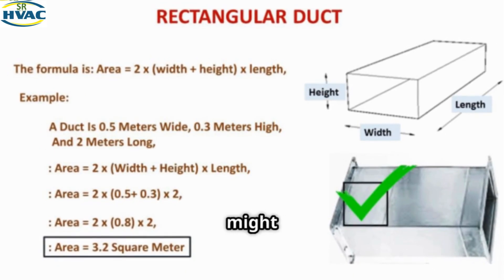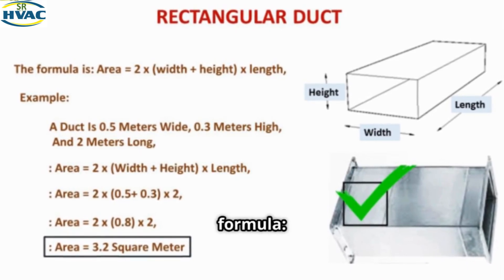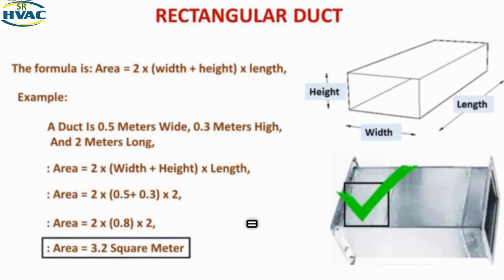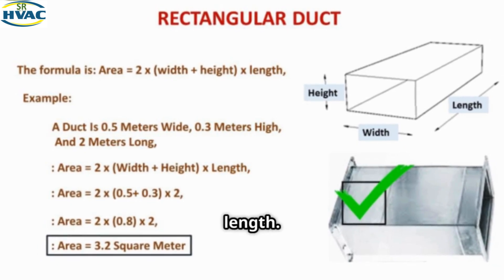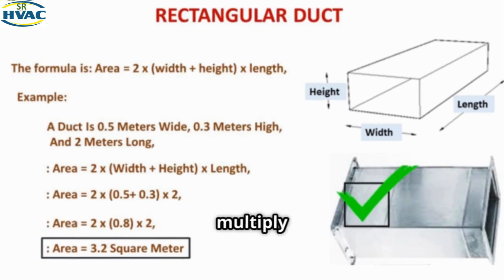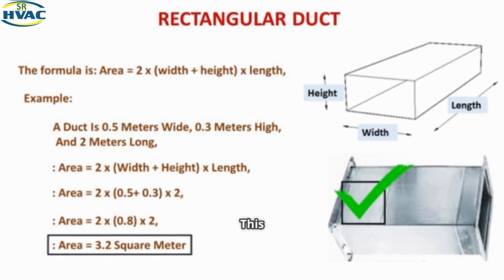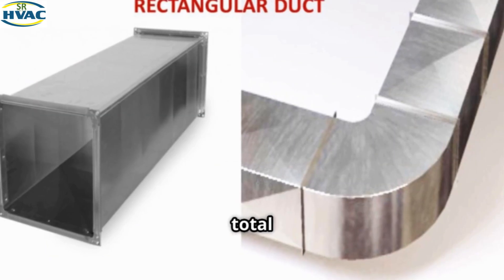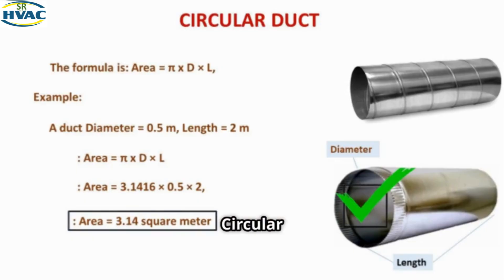0.3 meters high, and 2 meters long — these are common dimensions in a typical HVAC system. Using the formula: area = 2 × (width + height) × length, we get area = 2 × (0.5 + 0.3) × 2 = 3.2 square meters. This represents the total surface area of the rectangular duct.